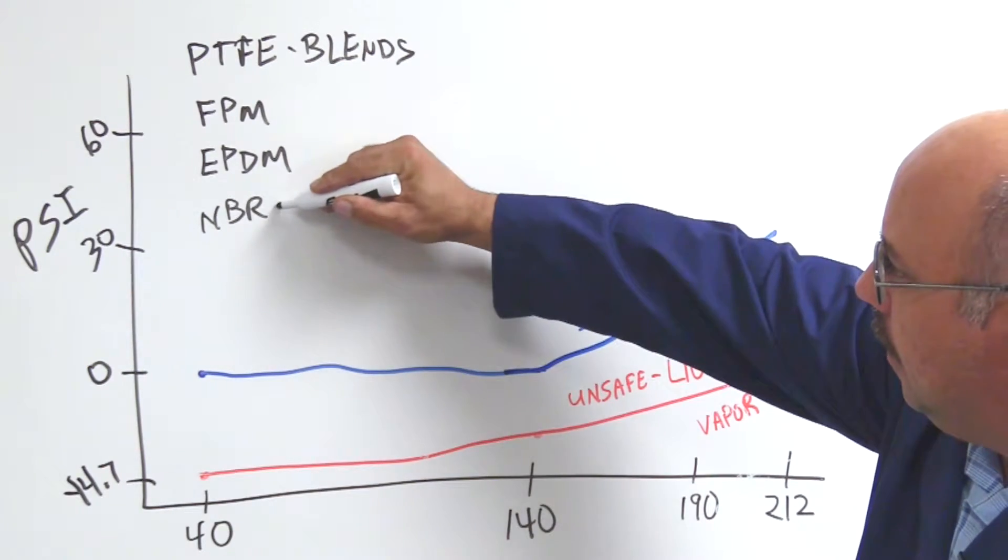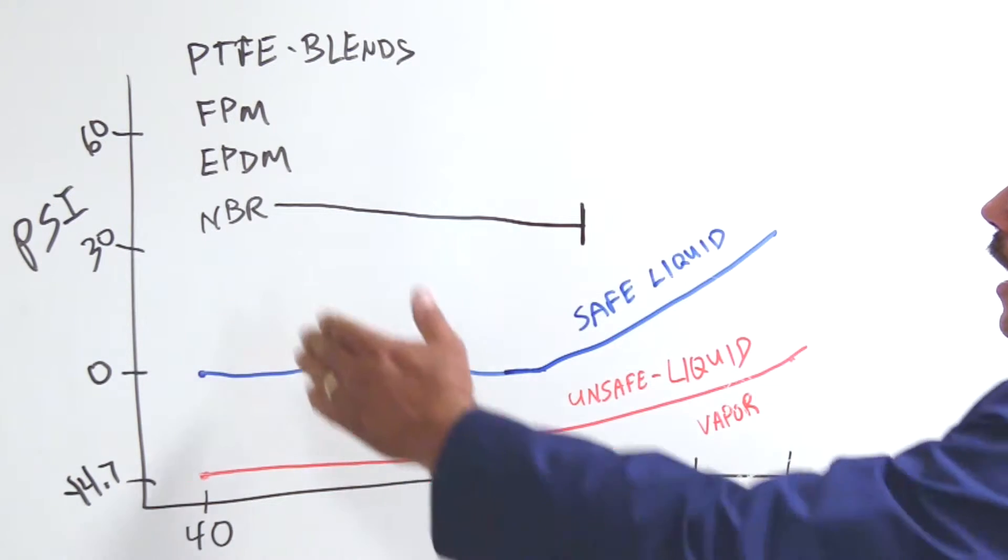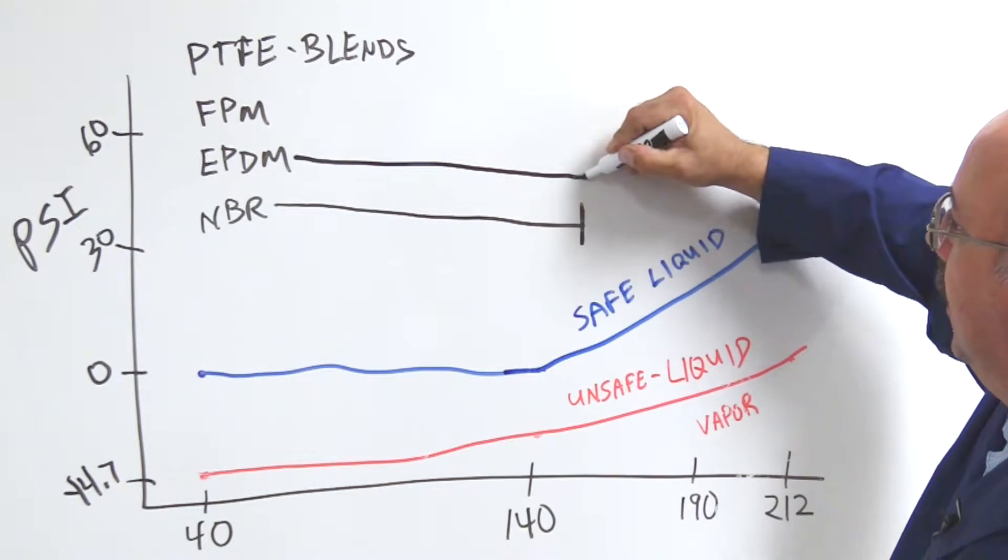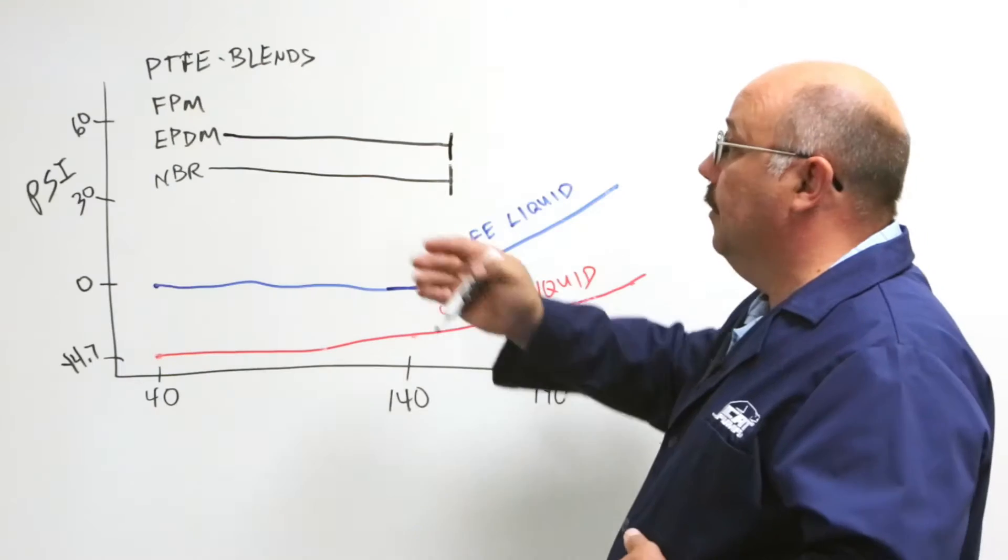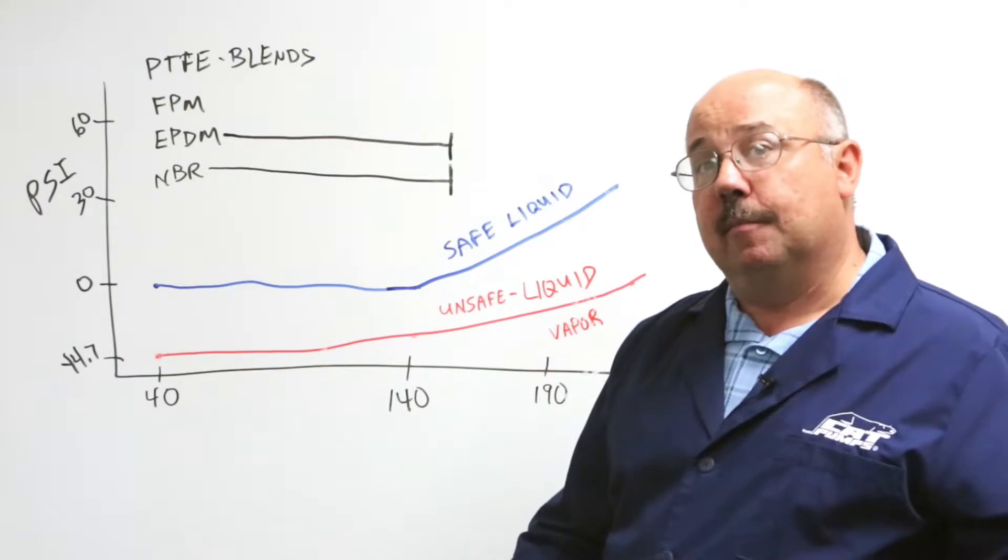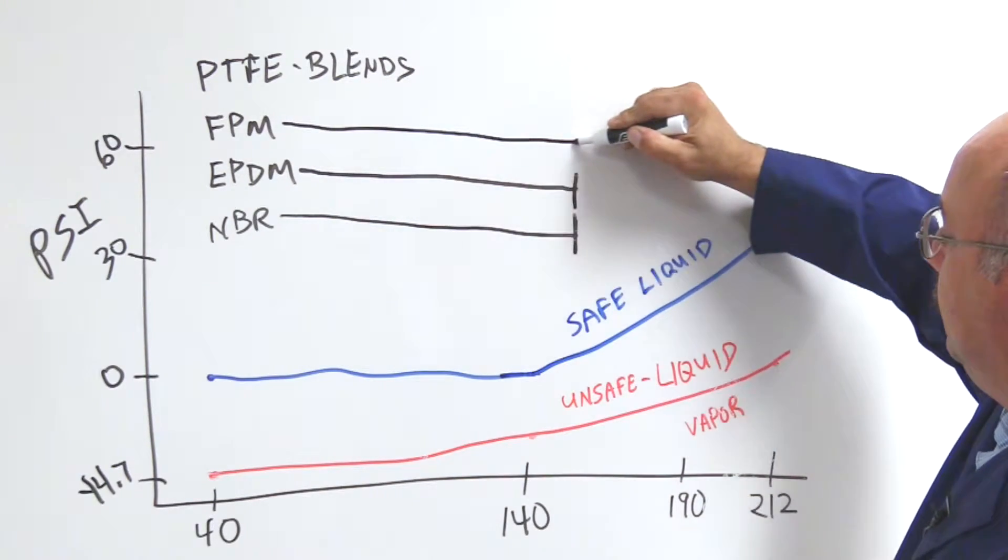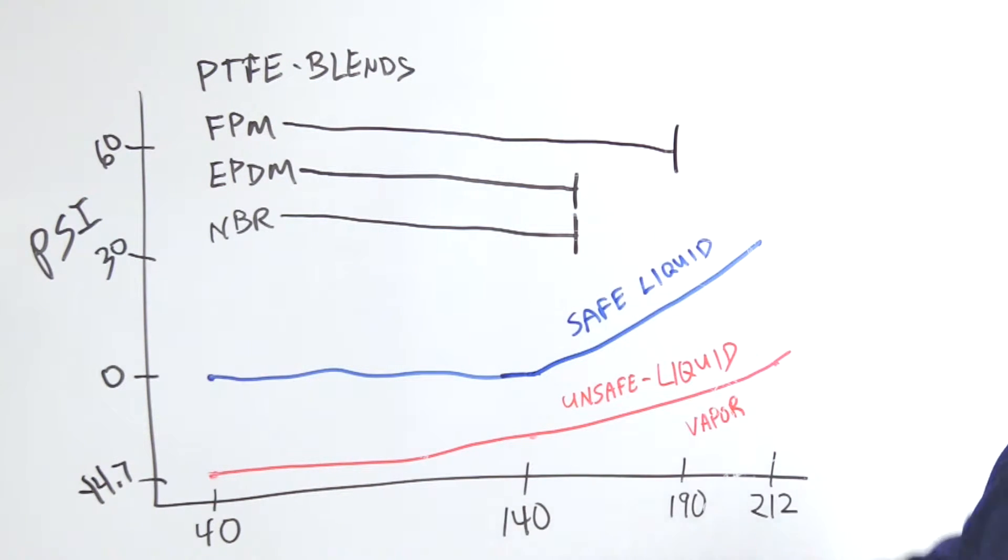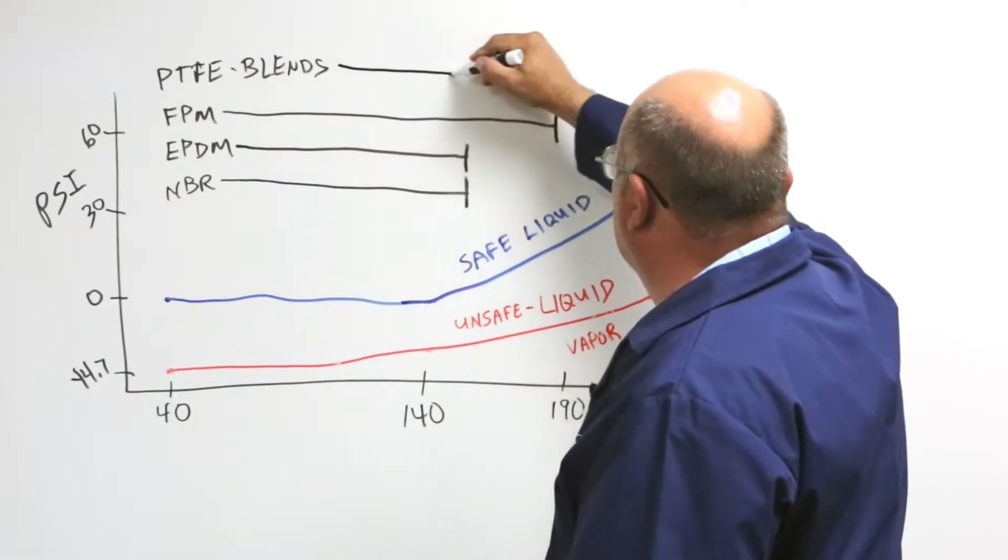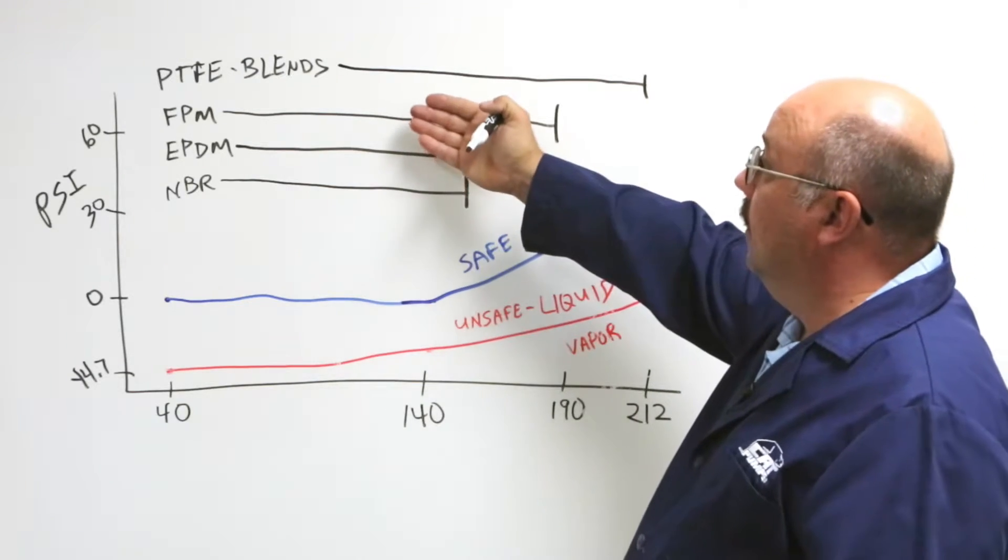Well with BUNA or NBR typically we can run 140, 150, 160. So about right here is where we stop using the BUNA because of temperature. The EPDM follows basically the same limitations. Now EPDM and NBR are two totally different materials and they're used depending on which liquid you're pumping, what's the best chemical compatibility for it. VITON is another compound, elastomeric compound, that'll take us up around the 190 range. And that's where that's good for. And so we have that possibility. And then the PTFE blends easily can handle temperatures up to 212.